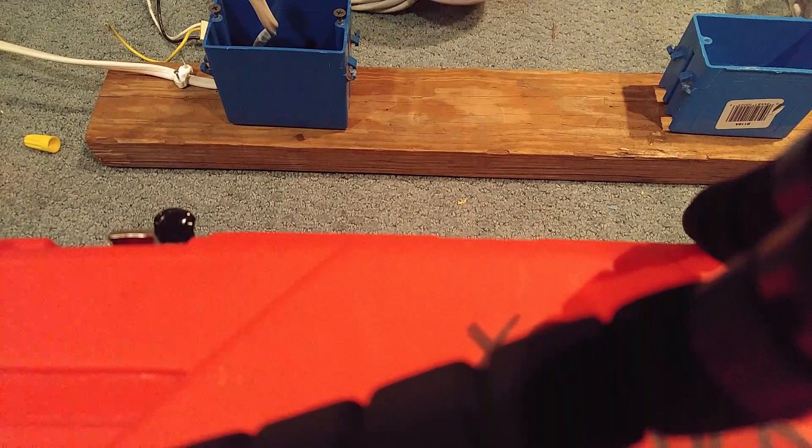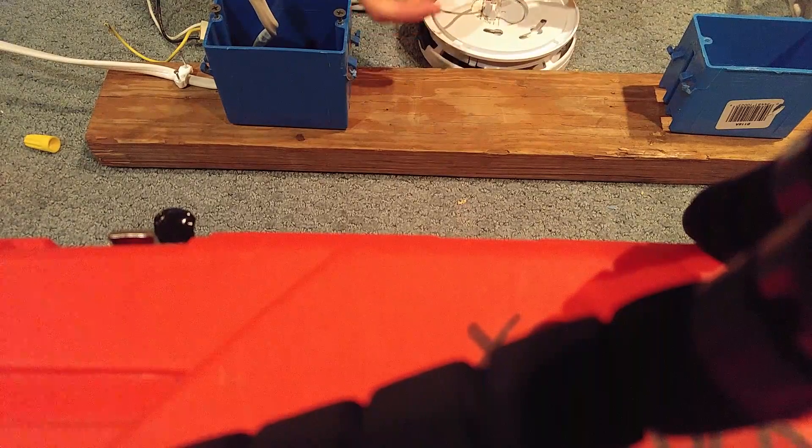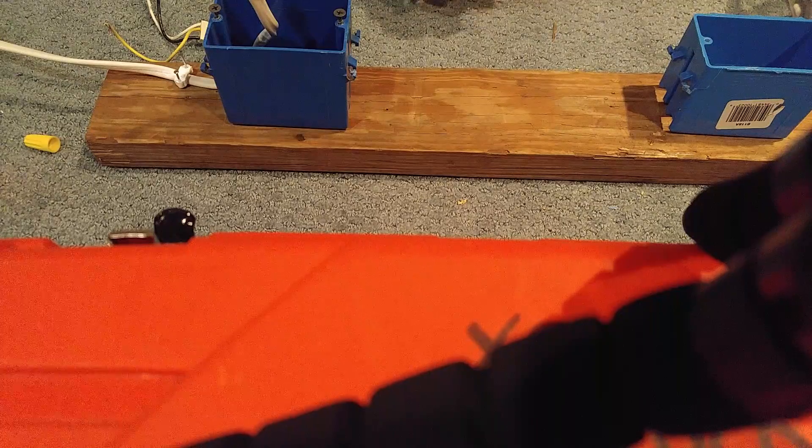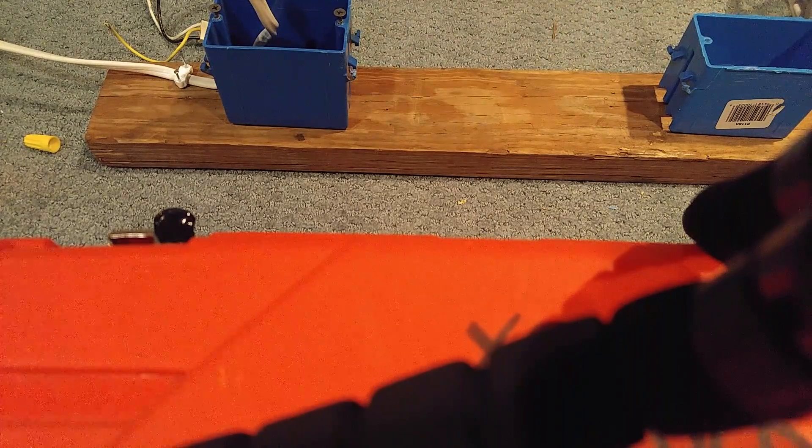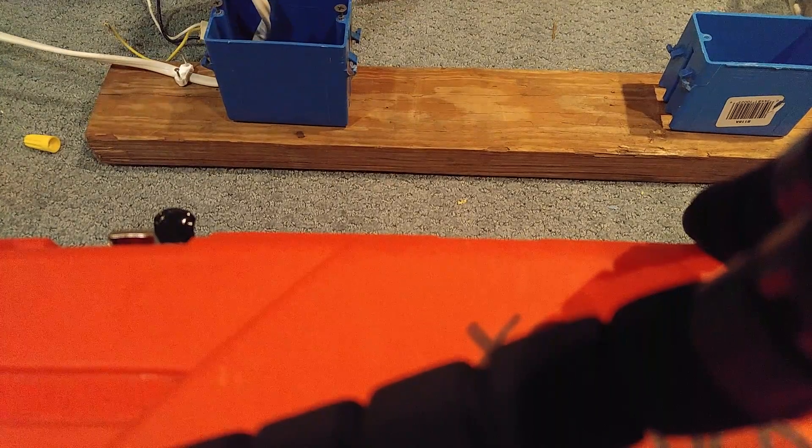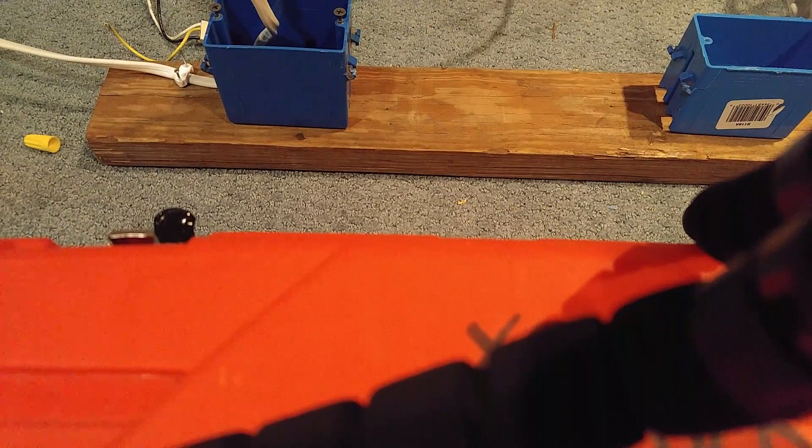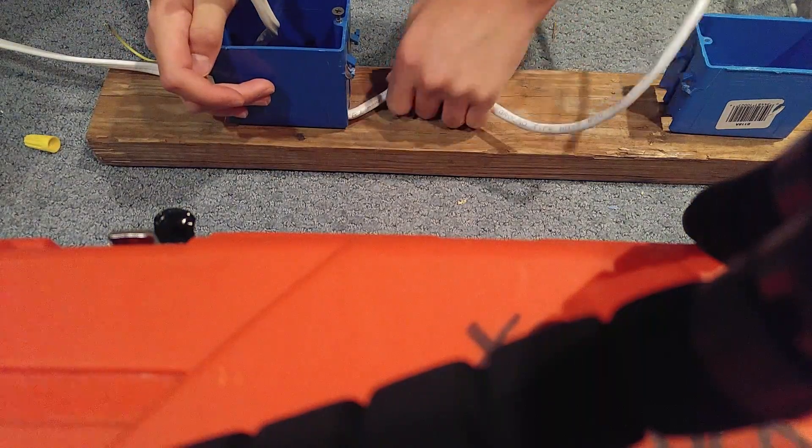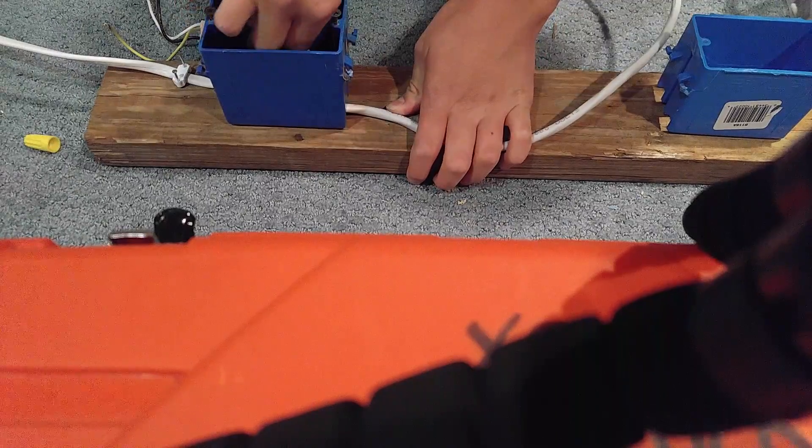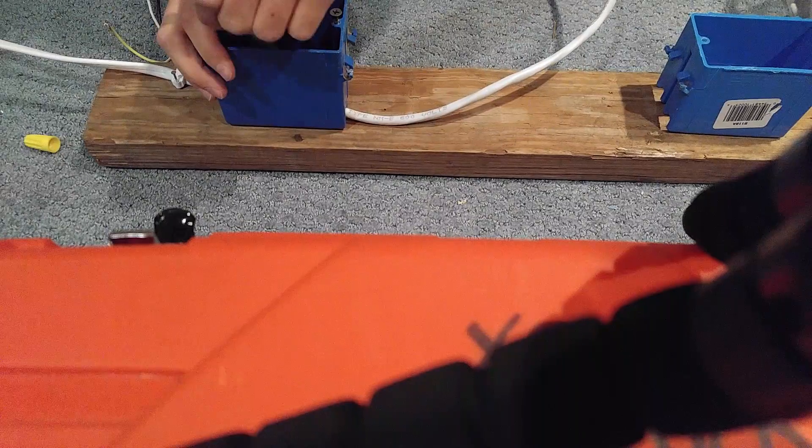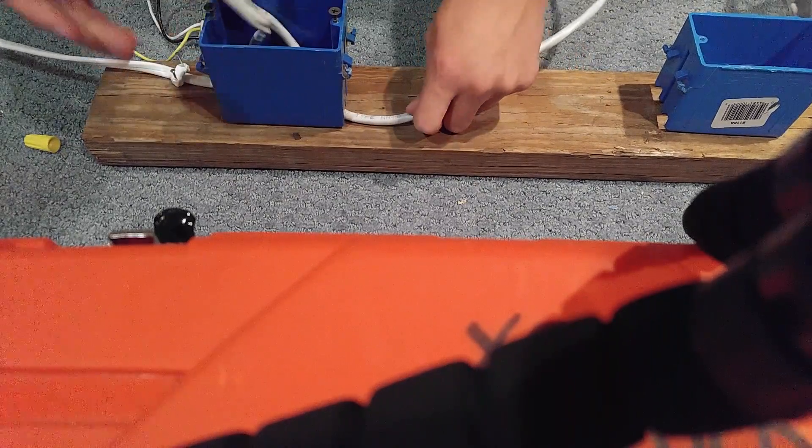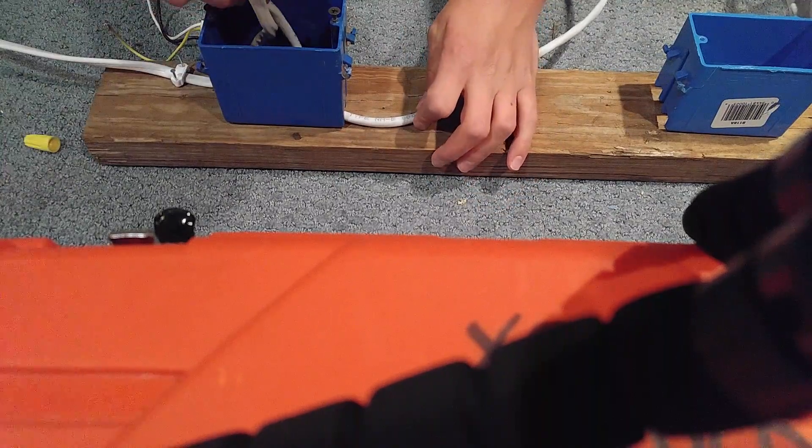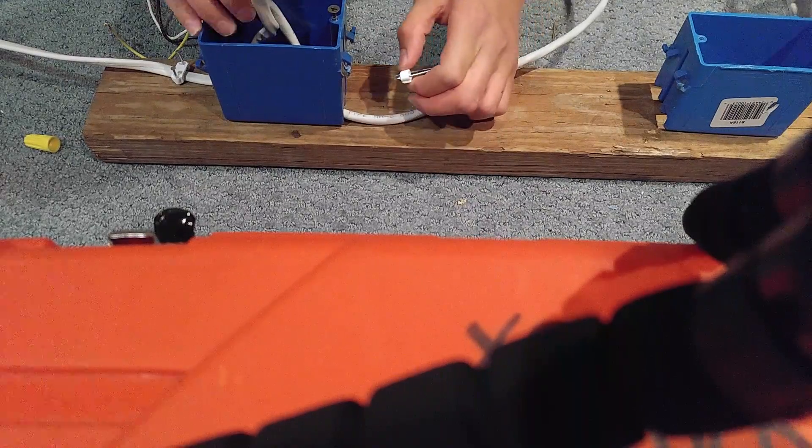So I got my 14.2 wire in. Now to your next box, I'm going to show you how many wires a smoke detector has. Hot, neutral, and a red wire for interconnect. I'll tell you about interconnect a little later. So you're going to need a 14.3 wire. I'm only going to show you two smoke detectors in this case, but you would just, after you run your 14.2 wire, you would just continue daisy chaining with 14.3 wires down the line. I like to put maybe 9 or 10 smoke detectors. I wouldn't exceed that much.